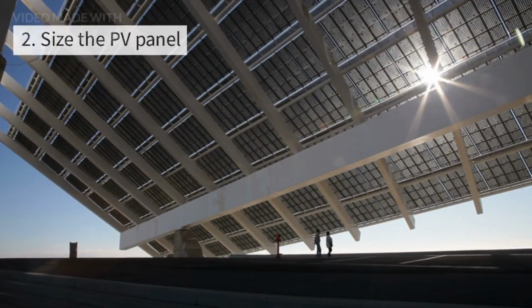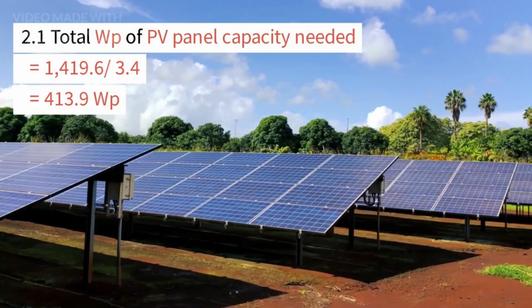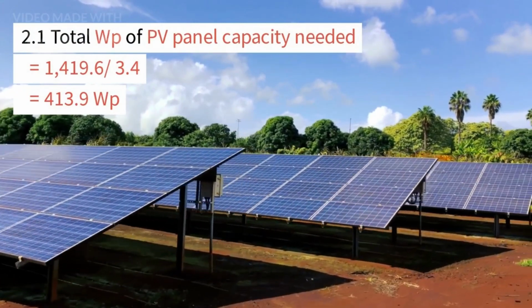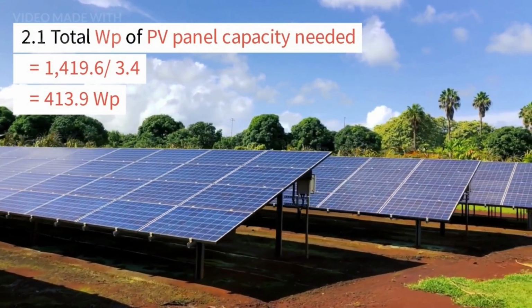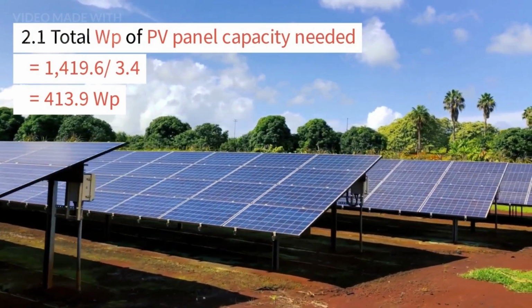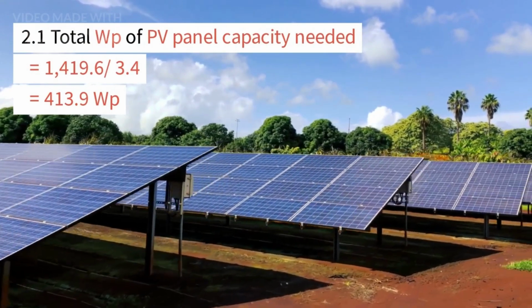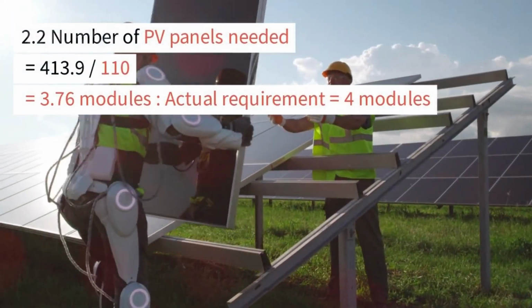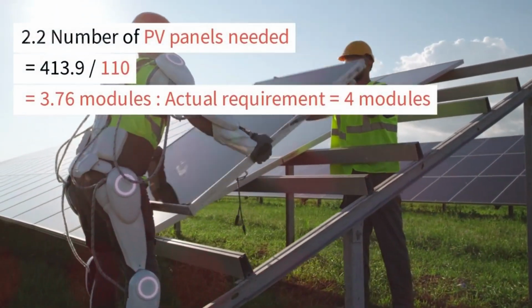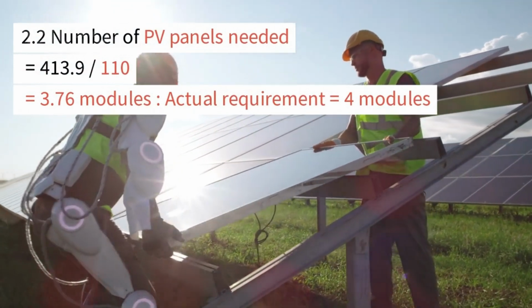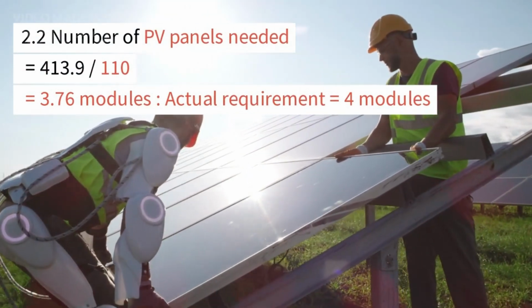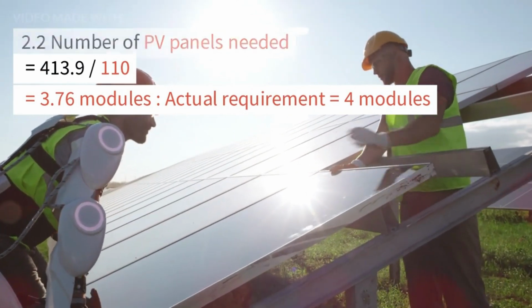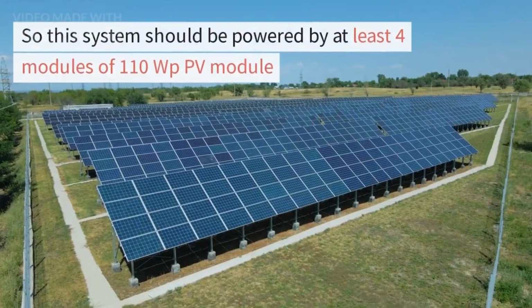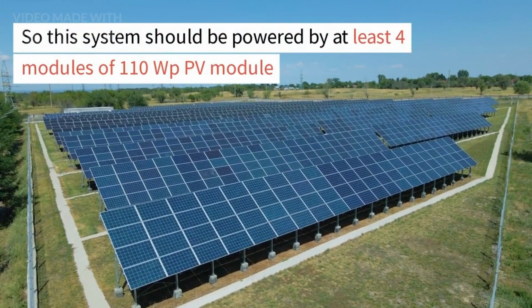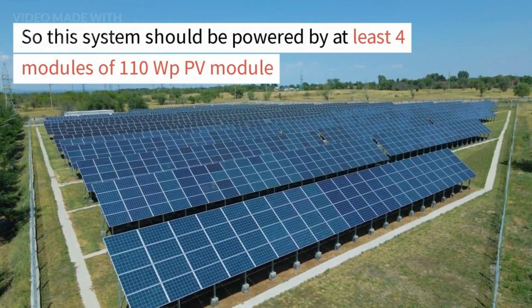2. Size the PV panel. 2.1 Total WP of PV panel capacity needed equals 1419.6 divided by 3.4 equals 413.9 WP. 2.2 Number of PV panels needed equals 413.9 divided by 110 equals 3.76 modules. Actual requirement equals 4 modules. So this system should be powered by at least 4 modules of 110 WP PV module.